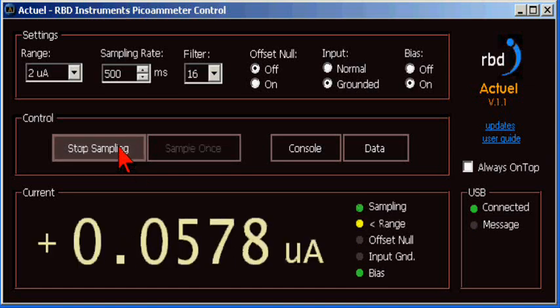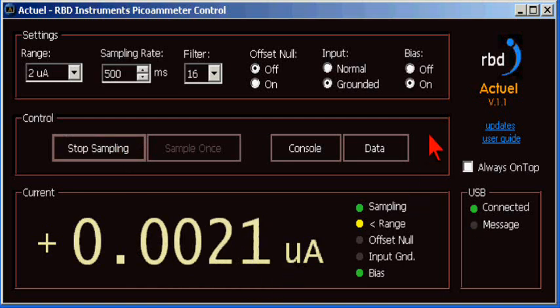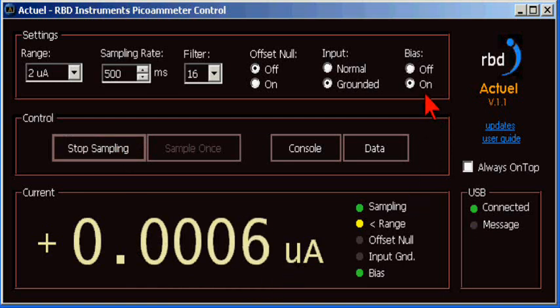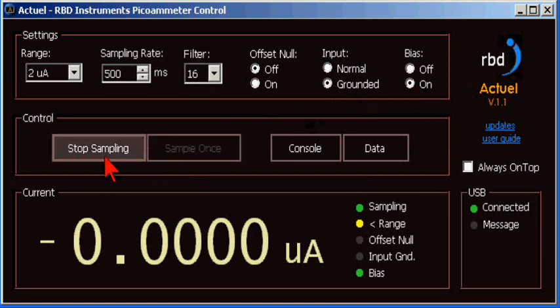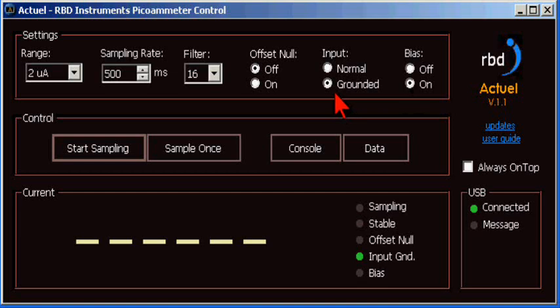When we measure current, the bias will be applied and the target will float up. With no input current, the reading is zero. When we stop measuring, the input will be shorted, which will ground the specimen stage. That keeps the target from charging when you're taking data, such as acquiring Auger data or XPS data. So for this mode, normally used on a spectrometer, grounds the target automatically when you're not measuring current.